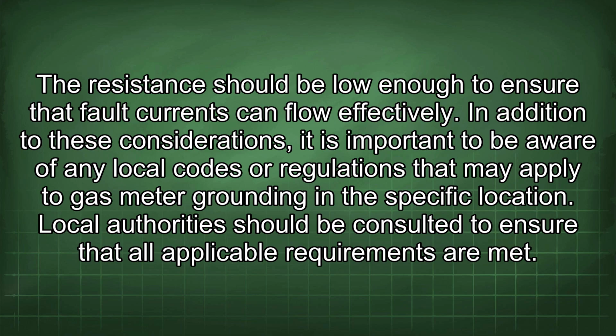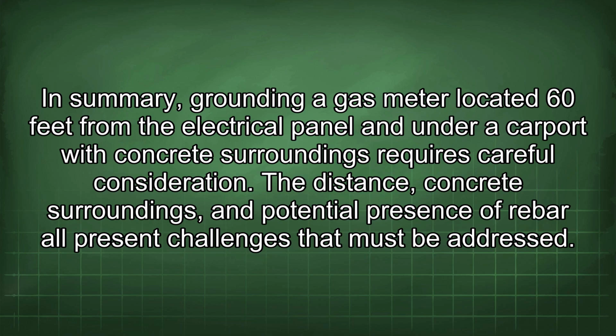In addition to these considerations, it is important to be aware of any local codes or regulations that may apply to gas meter grounding in the specific location. Local authorities should be consulted to ensure that all applicable requirements are met. In summary, grounding a gas meter located 60 feet from the electrical panel and under a carport with concrete surroundings requires careful consideration. The distance, concrete surroundings, and potential presence of rebar are all present challenges that must be addressed.